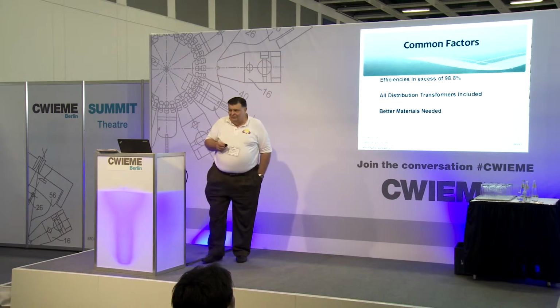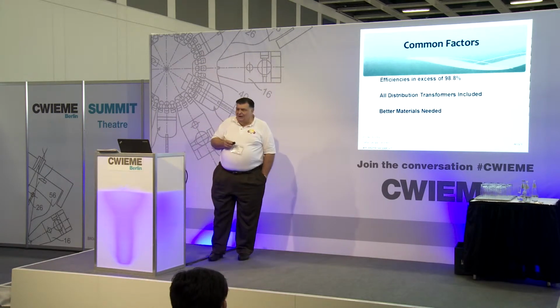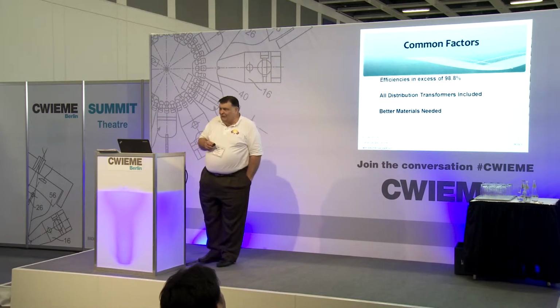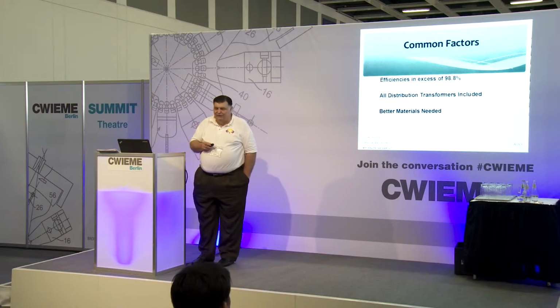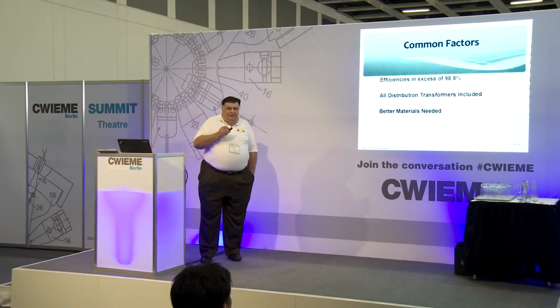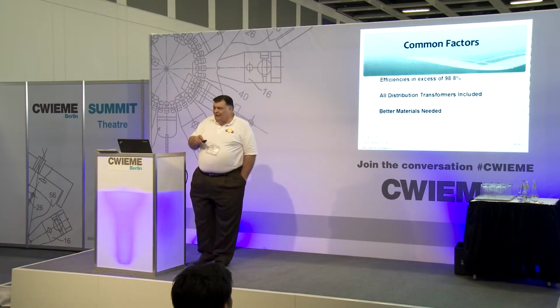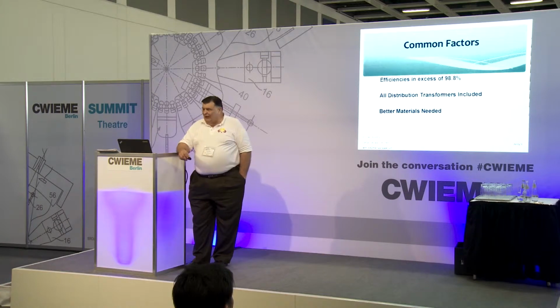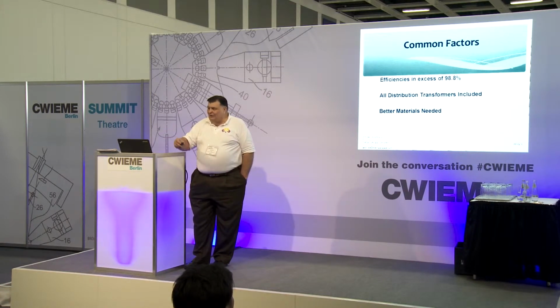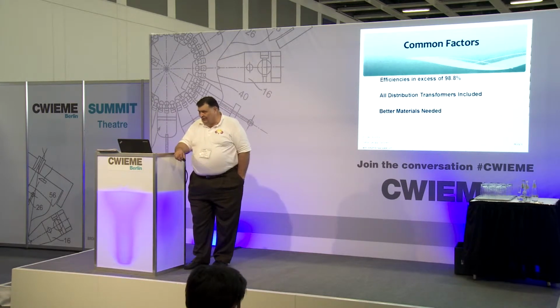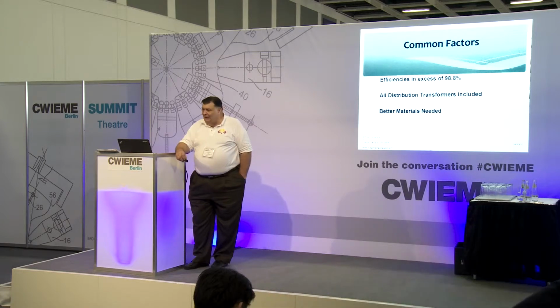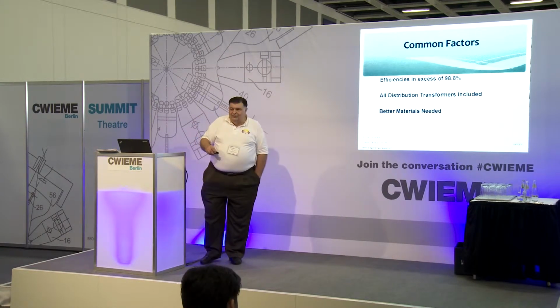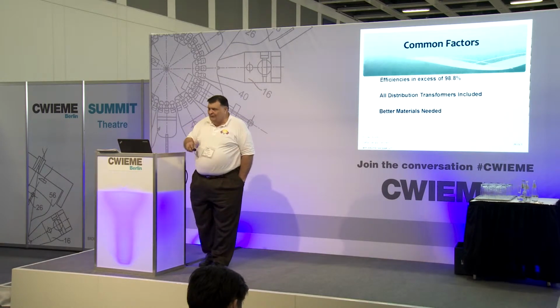What are the common factors? Efficiencies in excess of 98.8%, and for liquid immersed, efficiencies in excess of 99%. All distribution transformers are included. It used to be that if you were doing them for a company building a plant and they wanted a transformer inside the plant, that didn't have to meet the standards. If they were special projects, they didn't have to meet the standards. Under the new Japanese rule and the new American rule, every transformer made must meet the standard. And better materials are going to be needed. That's what we're going to talk about today.